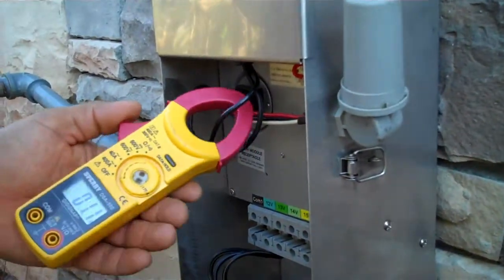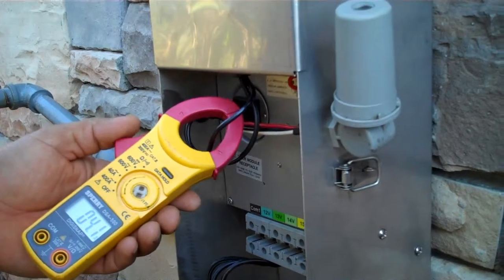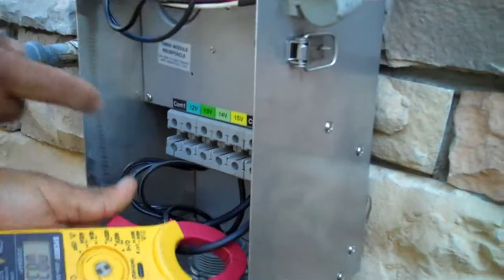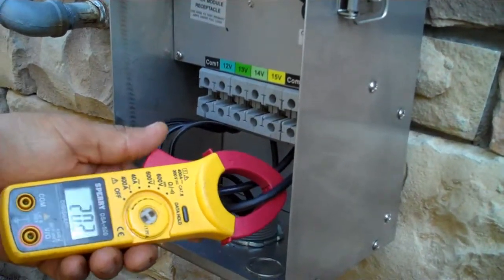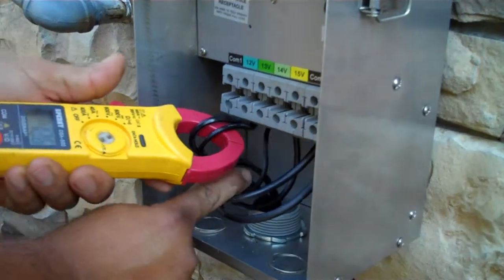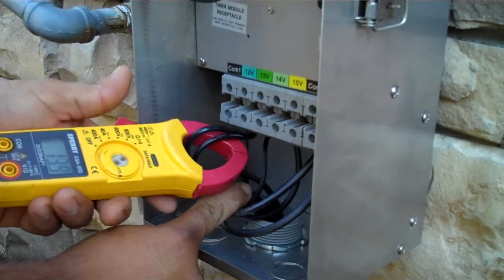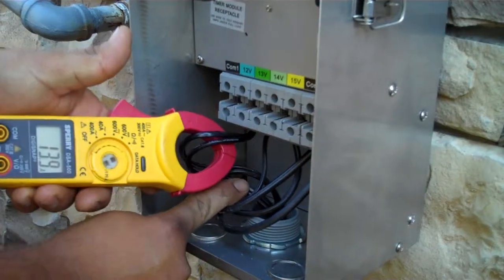Also, test the amp load on the low voltage side of the transformer. The low voltage breakers are rated at 25 amps, but we recommend that you do not exceed 21 amps on each common tap. This will increase the longevity of your transformer and low voltage breakers.